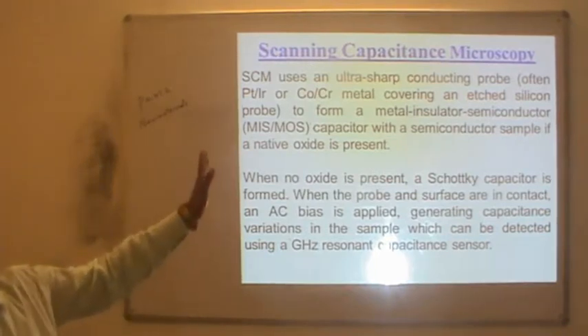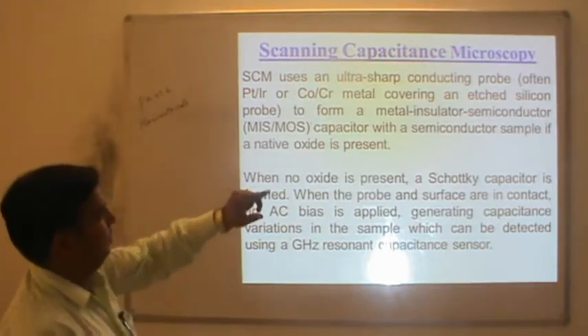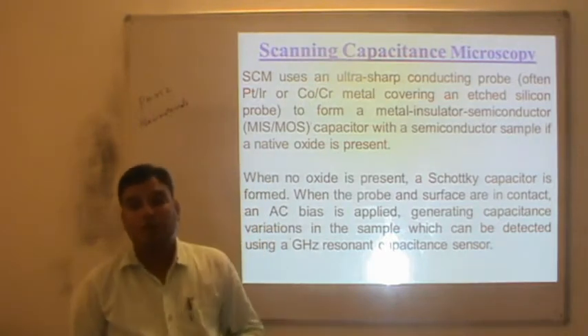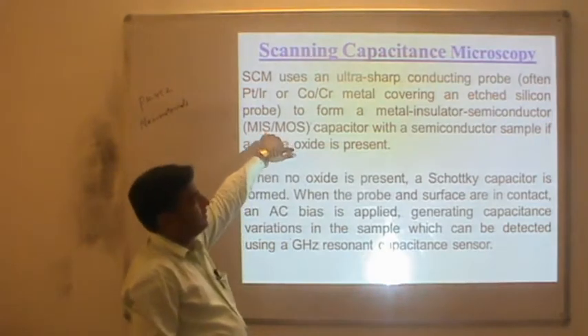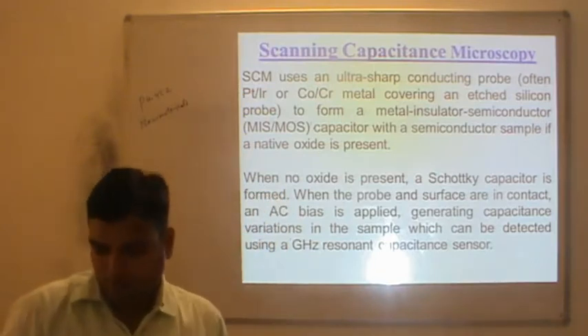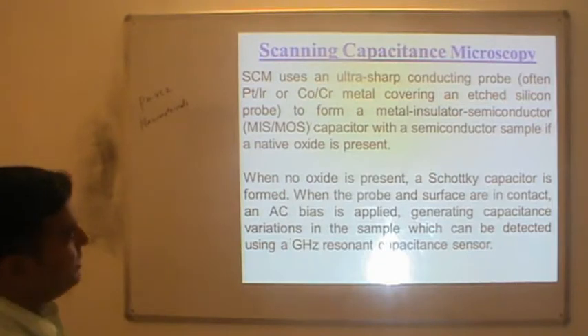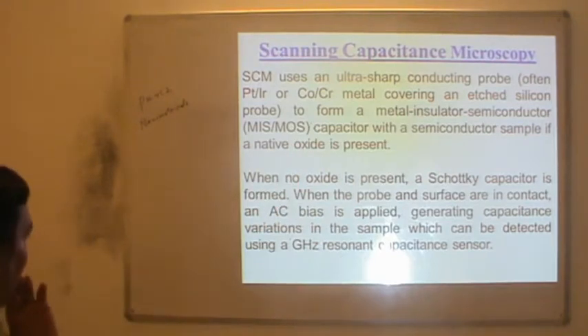The tip is coated with platinum-iridium or cobalt-chromium metal coating on silicon to form a metal-insulator-semiconductor capacitor with the semiconductor sample. If an oxide is present, it forms a metal-oxide-semiconductor structure giving information about the local capacitance between tip and sample. When no oxide is present, a Schottky capacitor is formed where the probe and surface are in contact and an AC bias is applied, generating capacitance variation that can be detected using a GHz resonant capacitance sensor.